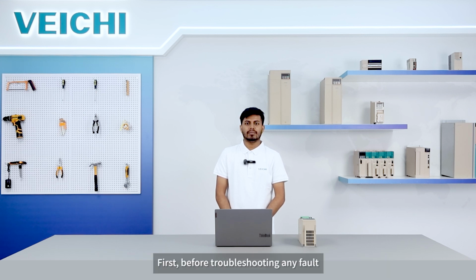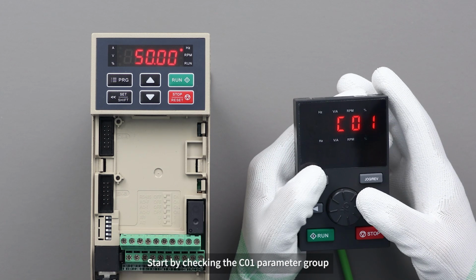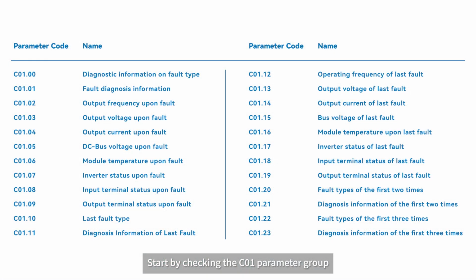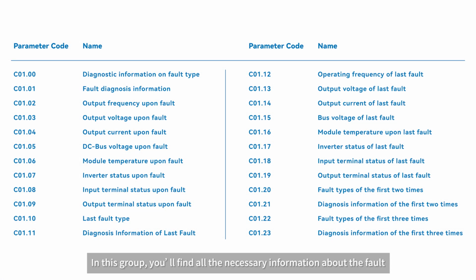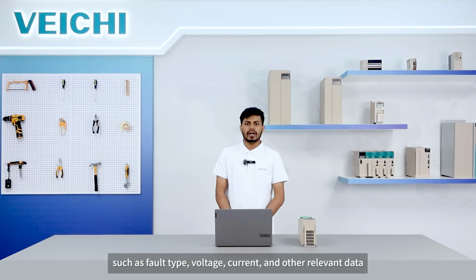Before troubleshooting any fault, you need to check the last fault status. Start by checking the C01 parameters group. In this group, you will find all the necessary information about the fault, such as fault type, voltage and current, and other relevant data.